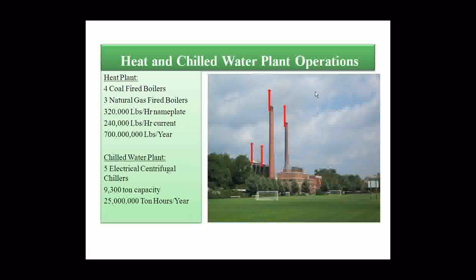Behind this plant we have the chill water plant, built in 1960, producing chilled water for the campus. Through these cooling towers we're dissipating thermal energy into the atmosphere. So this plant is throwing 25% of the heat value up the stack, and this plant is literally throwing thermal energy away, and the two plants don't connect—a challenge I've thought about for years, how we could connect and gain advantage by linking these two operations.